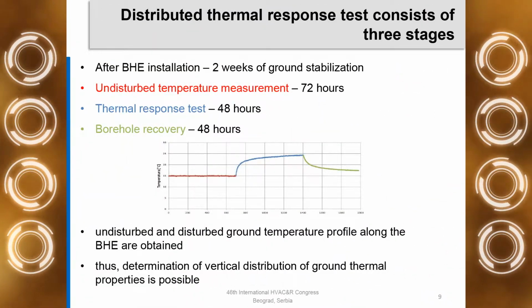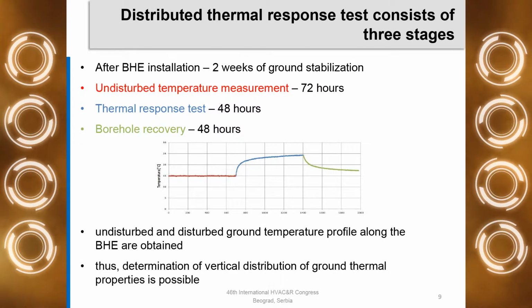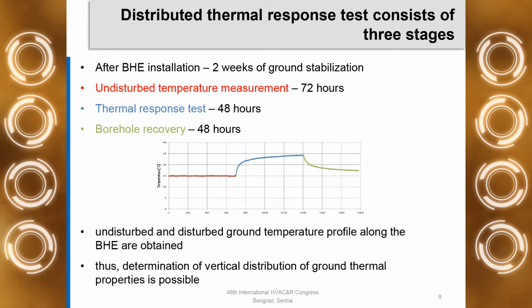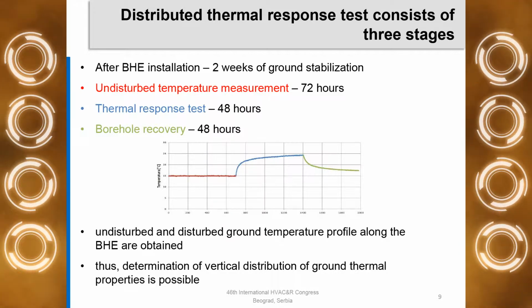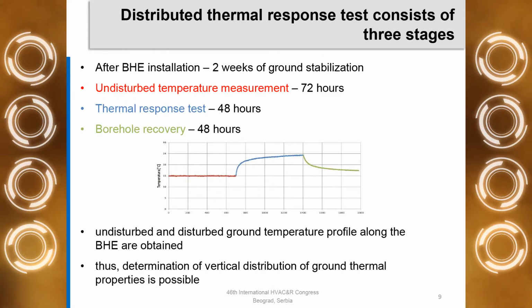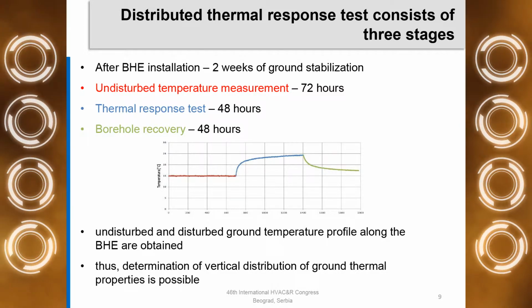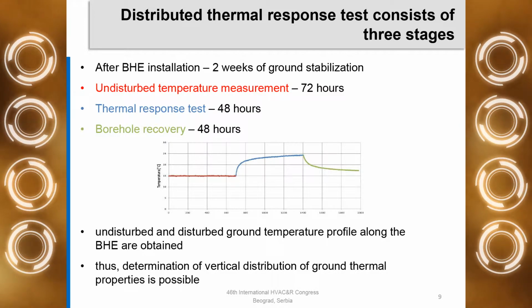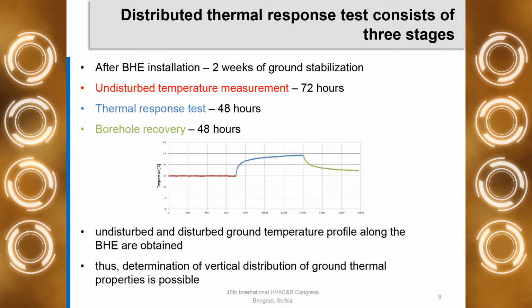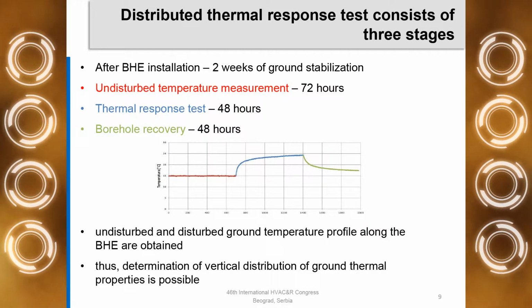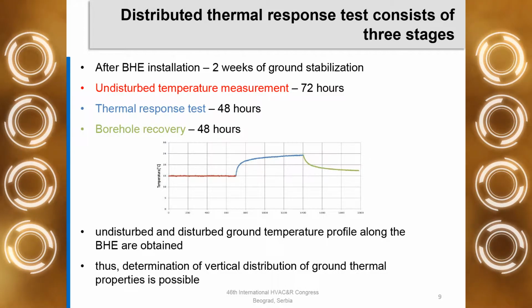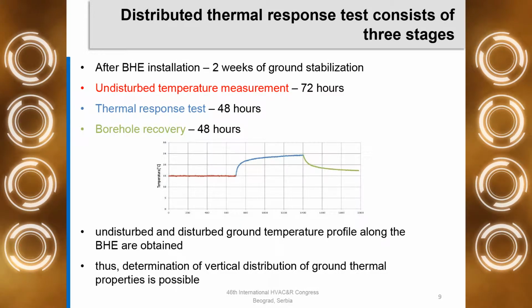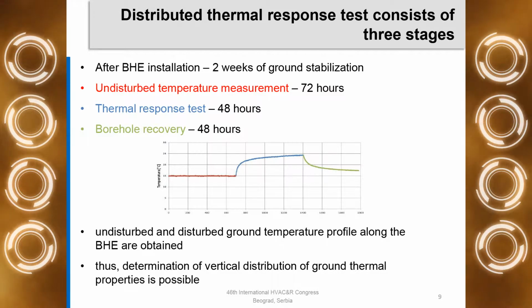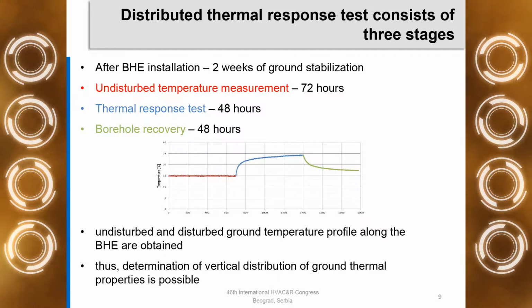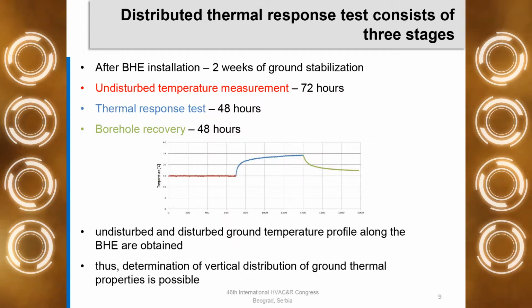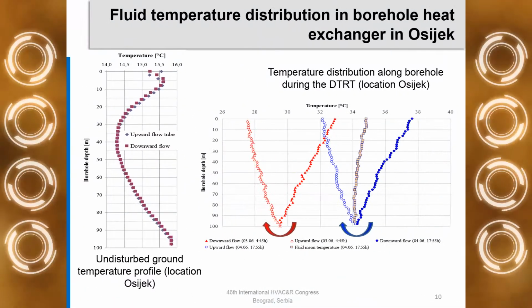As far as the distributed thermal response test, we separated 3 different phases. In the first phase, we obtained undisturbed temperature. In the second phase, it was the heating phase, where we monitored the response of the underground and borehole heat exchanger, and in the last phase, we monitored borehole thermal recovery. Basically, that allows us to obtain disturbed and undisturbed temperature profiles in the borehole heat exchanger, and therefore we were able to determine the vertical distribution of ground thermal parameters on all 8 locations.